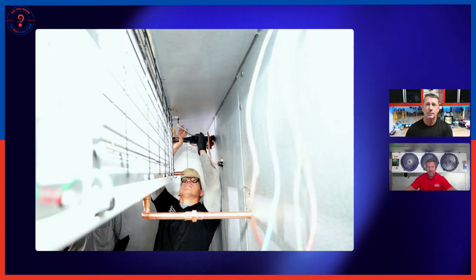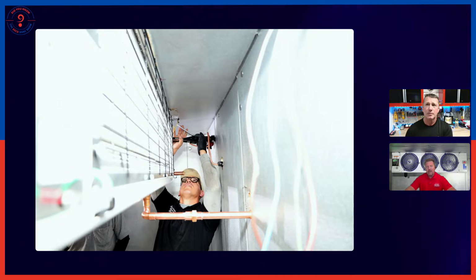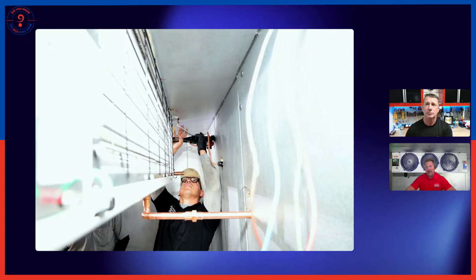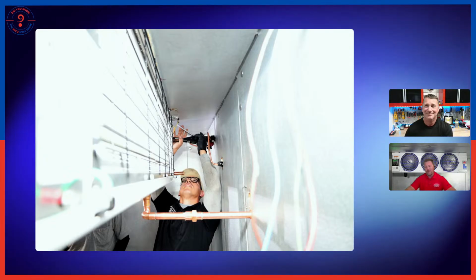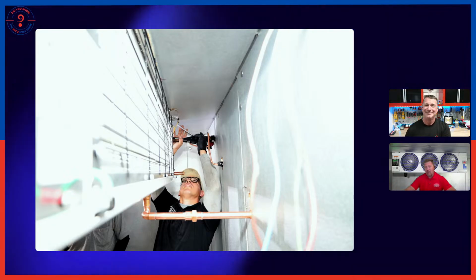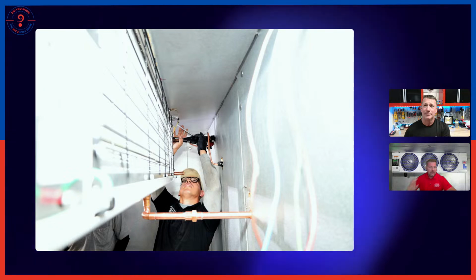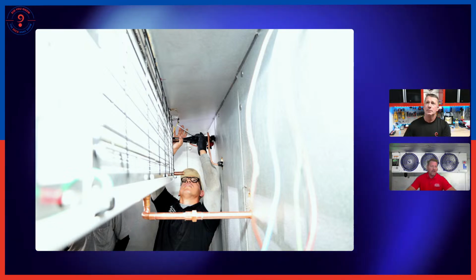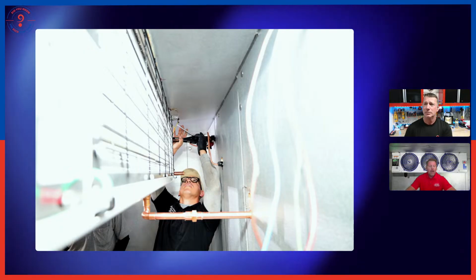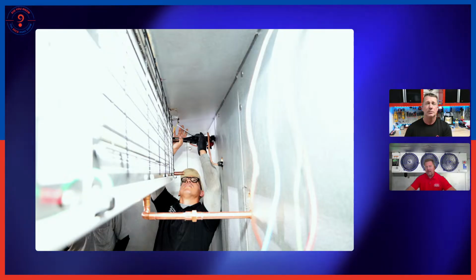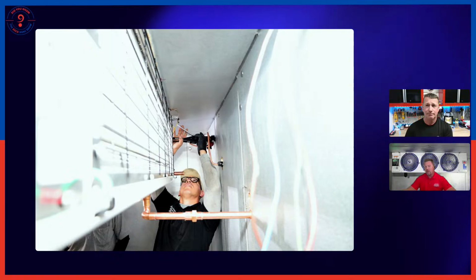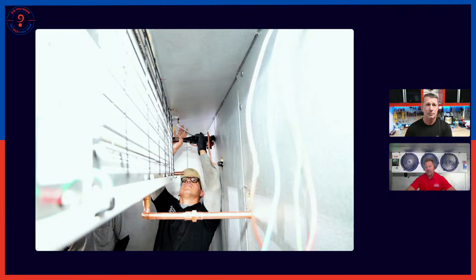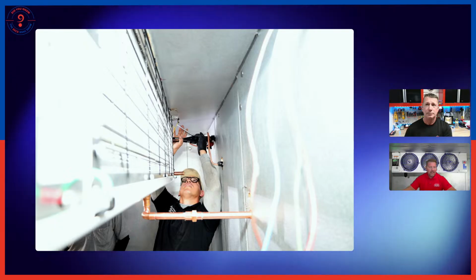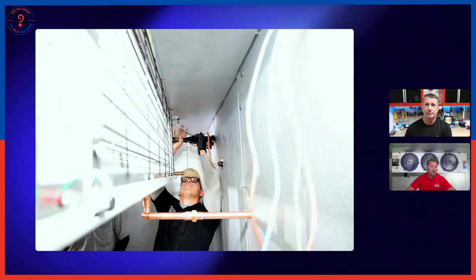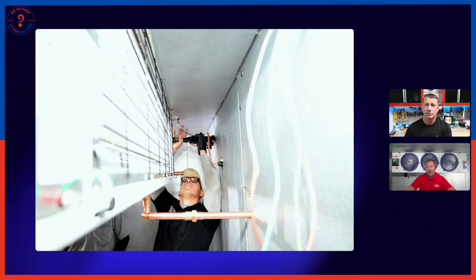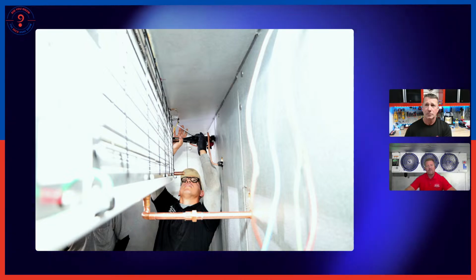Right. So, just to the people out there that are moving forward, we as manufacturers don't just put out these guidelines arbitrarily. There are some important reasons for it. And just because we might have gotten away with doing things differently in the past, the tighter things get and the more, and I don't want to use the word dangerous because I don't feel A2Ls are dangerous, but there are precautions that need to be taken that didn't exist 30 years ago. And we do need to be very conscious of those and avoid putting ourselves in situations that could be dangerous, because we are dealing with a flammable gas, partially flammable. It's still something we need to have a healthy respect for.